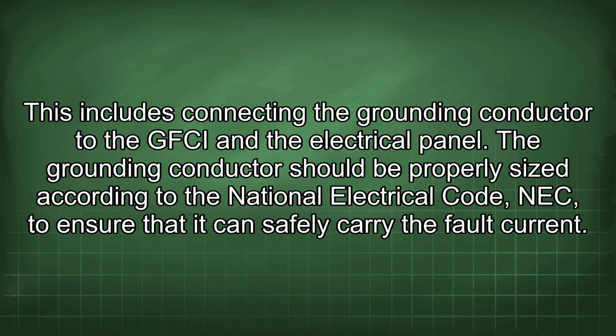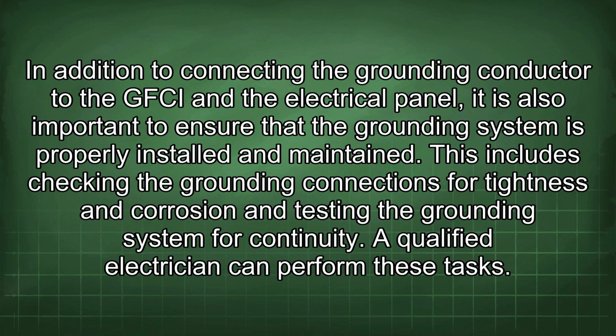The grounding conductor should be properly sized according to the National Electrical Code (NEC) to ensure that it can safely carry the fault current. In addition to connecting the grounding conductor to the GFCI and the electrical panel, it is also important to ensure that the grounding system is properly installed and maintained. This includes checking the grounding connections for tightness and corrosion and testing the grounding system for continuity. A qualified electrician can perform these tasks.